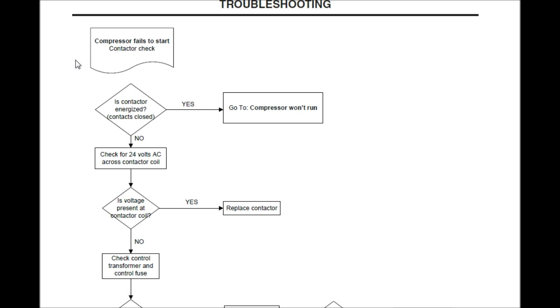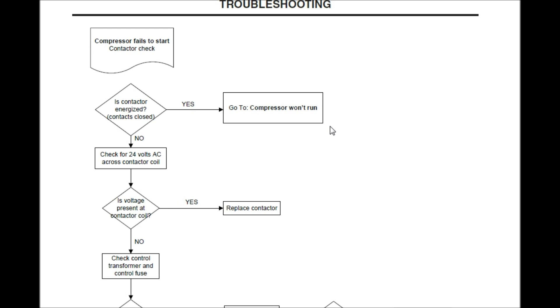Troubleshooting. Compressor fails to start, contactor check. Let's get started. Is the contactor energized? Has it pulled in? Let's say it has and we don't have anything. So what this is saying is telling us to go to compressor won't start. That's going to be another flow chart. We'll get to that in the future here.